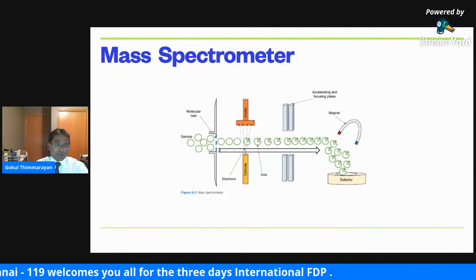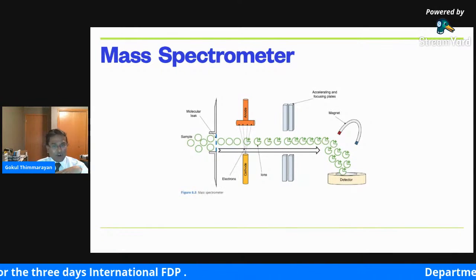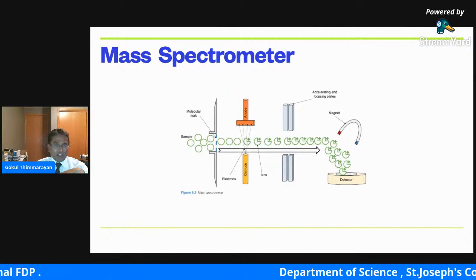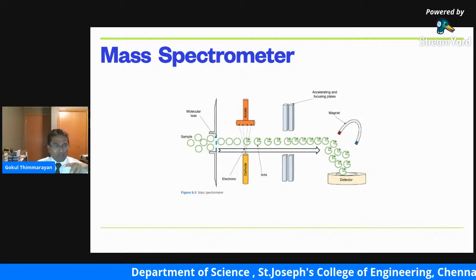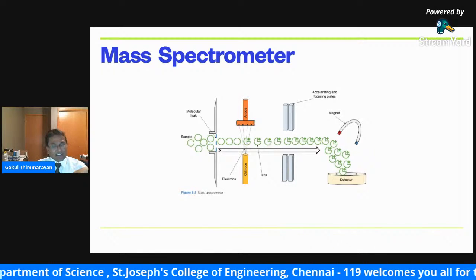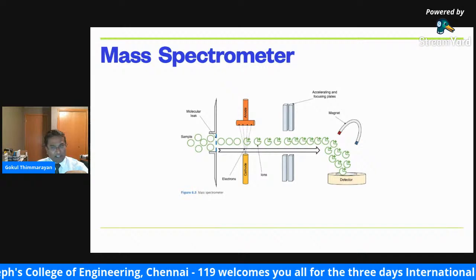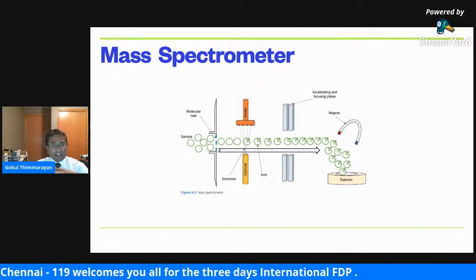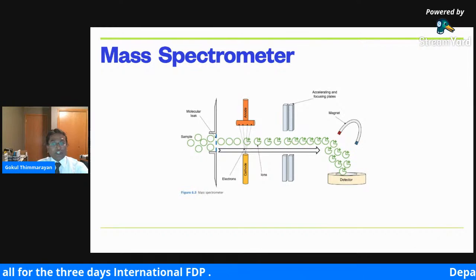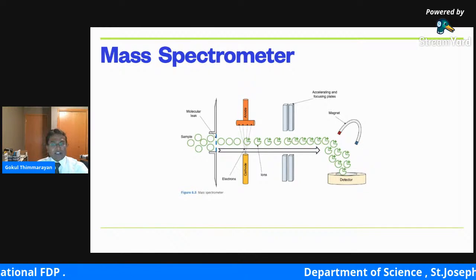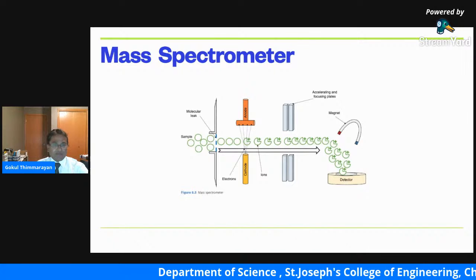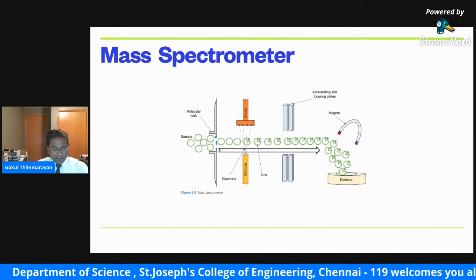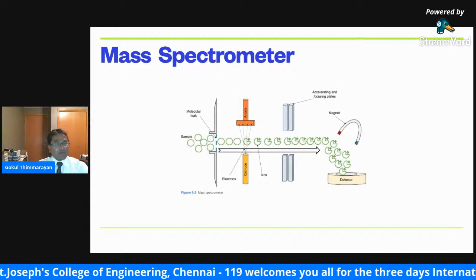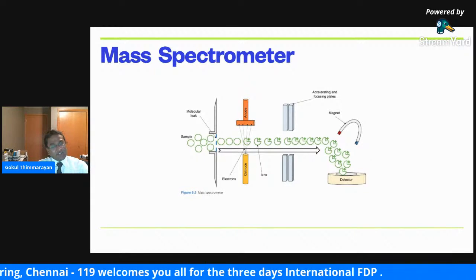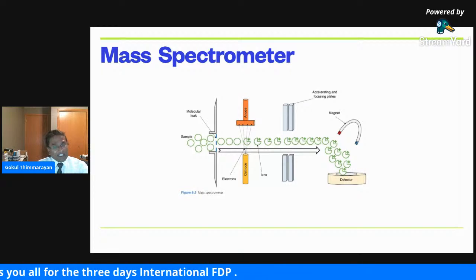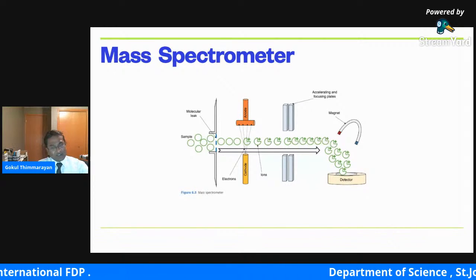And the other method is mass spectrometer. Here, the sample gas which we want to analyze is passed through the apparatus, where it gets bombarded with electrons, and the gas gets ionized. And this ionized gas is accelerated and allowed to pass through a magnetic field. When this ionized molecule passes through the magnetic field, it's deflected in a certain pattern which is unique to each gas type. So based on the deflection and the extent of deflection, it identifies the gas and its concentration. So these are the various methods: paramagnetic analyzer, infrared, Raman scattering, mass spectrometer. These are the physical principles which we utilize to identify the medical gases and their concentration.